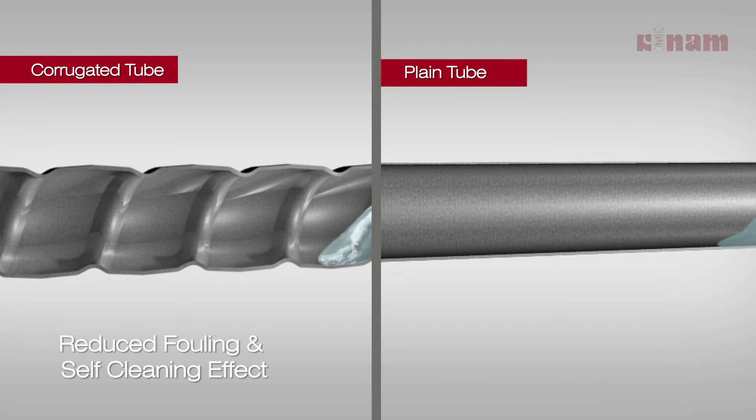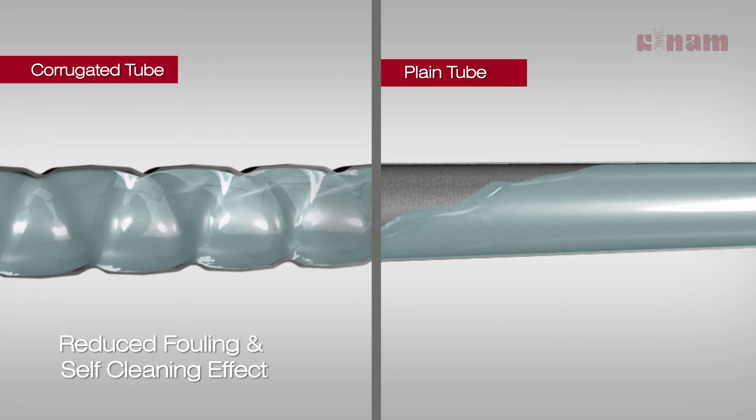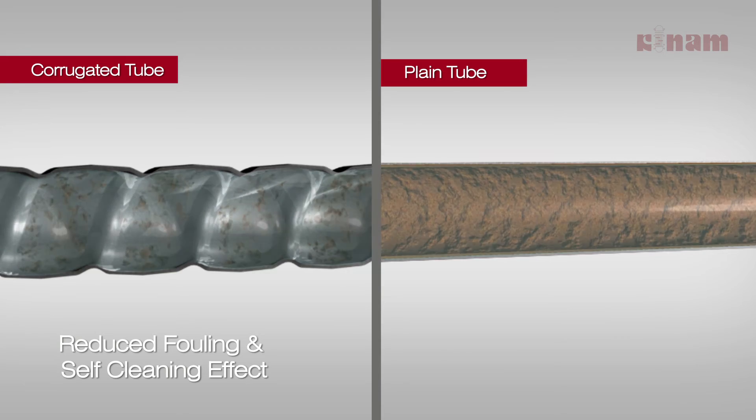Higher peripheral turbulence due to corrugations does not allow the suspended solids in the fluid to settle on the tubes, thus giving it a self-cleaning effect, which results in reduced fouling. This ensures longer running time without stopping for cleaning.